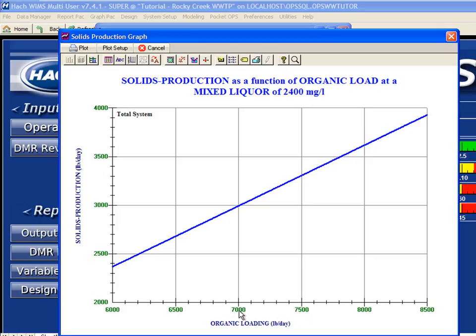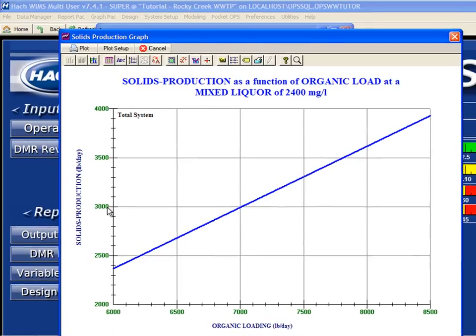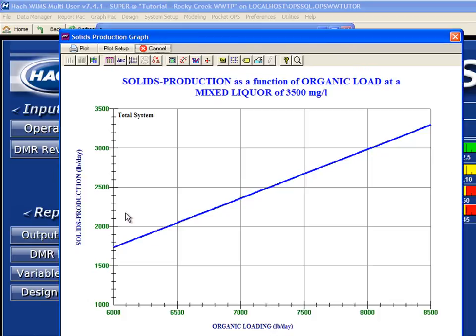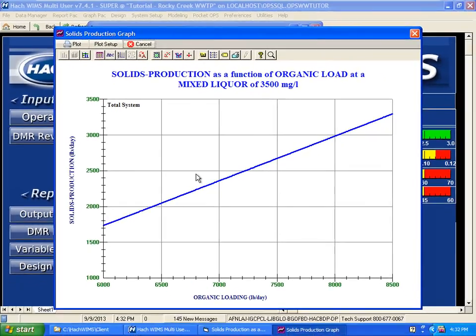Reading this graph — if our influent organic load is 7,000 pounds, given our current operating conditions, we're going to produce about 3,000 pounds of solids. Now I can play a what-if game and say I want to run a mixed liquor of 3,500 given the same operating conditions. At 7,000 organic load, I'm going to produce 2,400 pounds of solids.